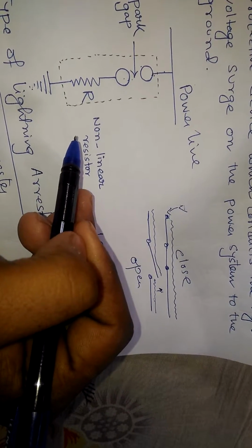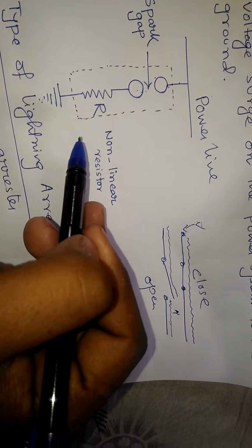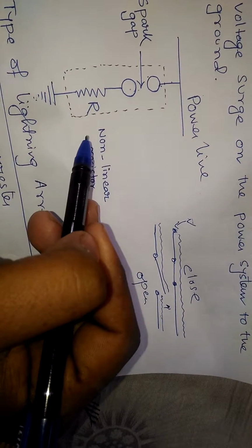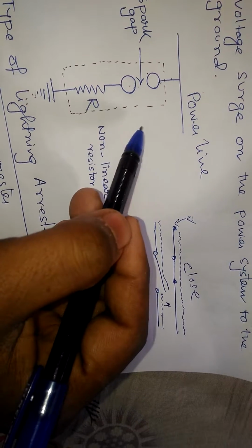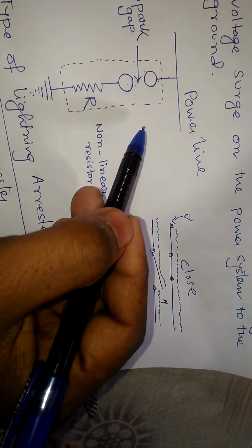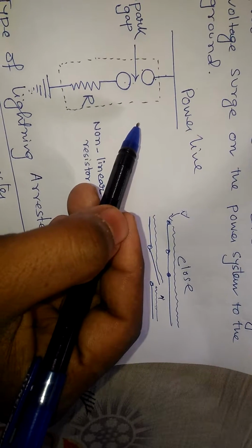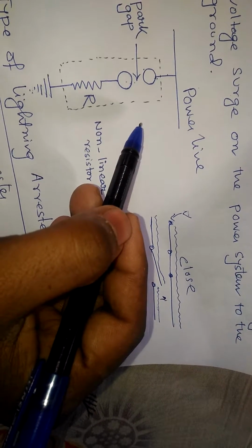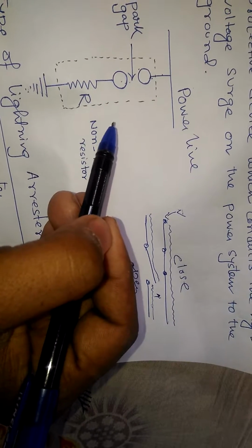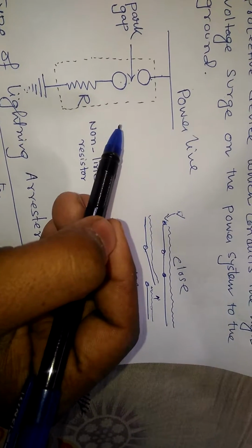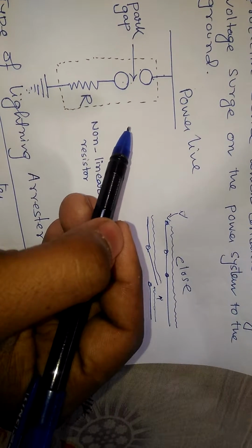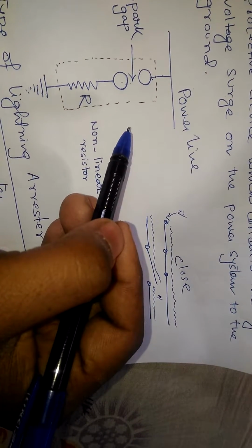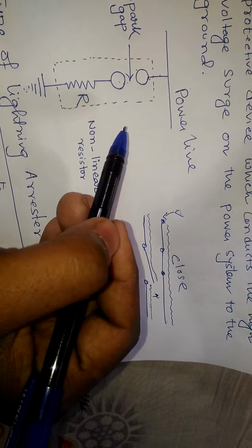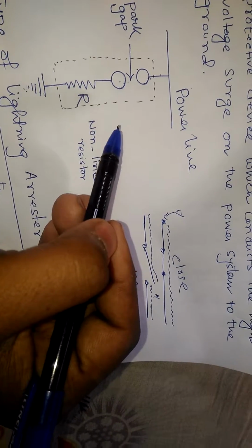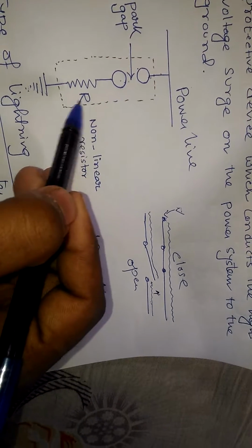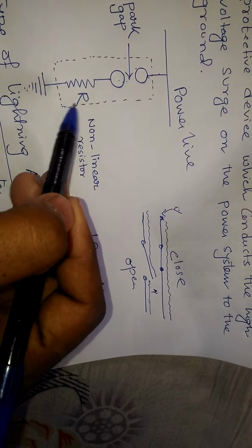It is worthwhile to mention the function of the nonlinear resistor in the operation of the arrestor. As the gap sparks over due to overvoltage, the arc would be a short circuit on the power system and may cause power follow current in the arrestor. Since the characteristic of the resistor is to offer higher resistance to lower voltage, it prevents the effect of a short circuit. After the surge is over, the resistor offers high resistance to make the gap non-conducting.